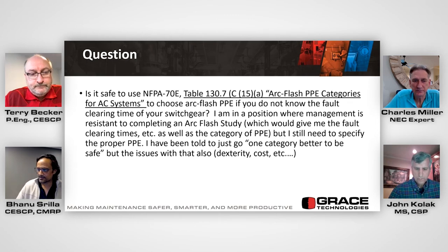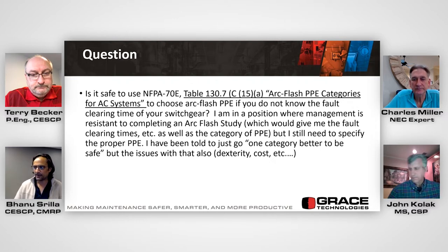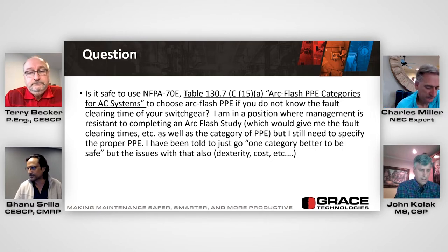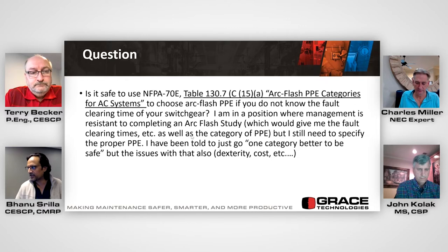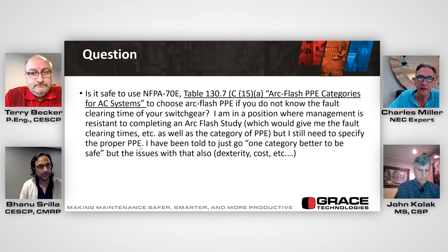This is a long question. Is it safe to use NFPA 70E table 130.7(C)(15)(a) arc flash PPE categories for AC systems to choose arc flash PPE if you do not know the fault clearing time of your switchgear? The person asking is in a position where management is resistant to completing the arc flash study, which would give them the fault clearing times and the category of PPE, but they still need to specify the proper PPE. So they've been told to use one category higher to be safe—or what do you think? The issues with that are cost, dexterity, etc. This is a practical question someone emailed in and asked me to put in front of you.